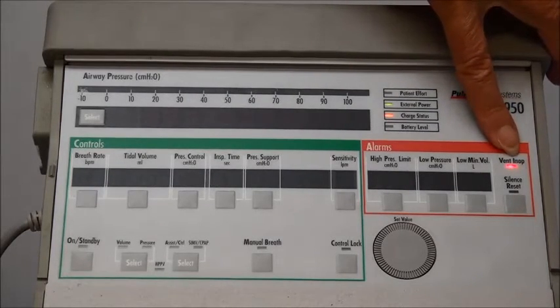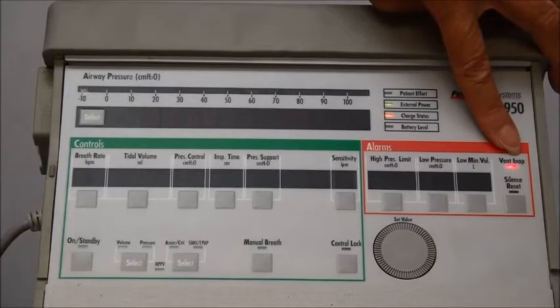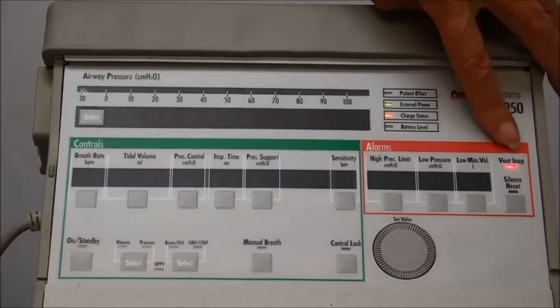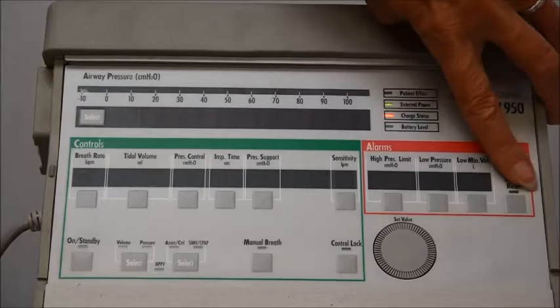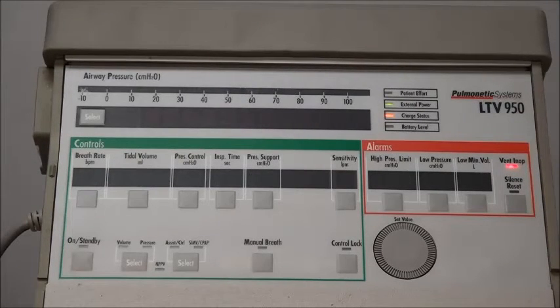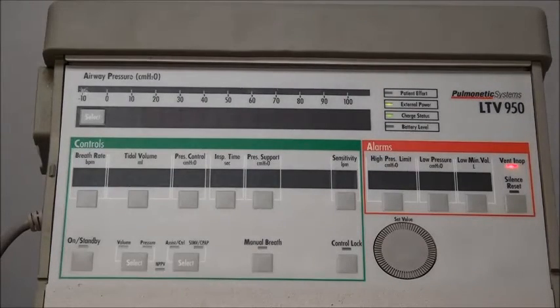If we look over here, we can see where there's a vent in-op light, and it's telling us that the ventilator is shut off right now. And you will see that light whenever you come in and your ventilator is off, or when you shut the ventilator off, that vent in-op light will come on. You also have a silence reset button. So you would be able to silence an alarm, and anytime you get an alarm, that would be what you would press to reset it. So your high pressure alarm, that would be set according to your patient's pressure, and anytime your patient generated a pressure that was above this alarm setting, you would get an alarm.